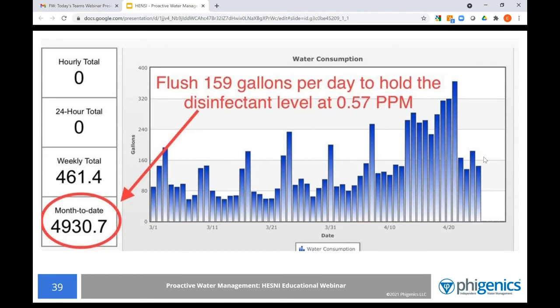You can see that some days we only needed to flush 50 gallons, and at other days we needed to flush 300 gallons. And that difference is due to all those different impacts on the disinfectant levels in a hot water loop. And so really gaining control over these, you're never going to overflush or underflush. And having the data visibility really allowed us to quantify that from an efficiency standpoint.